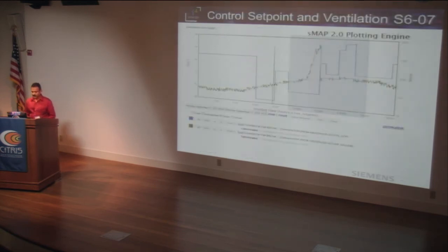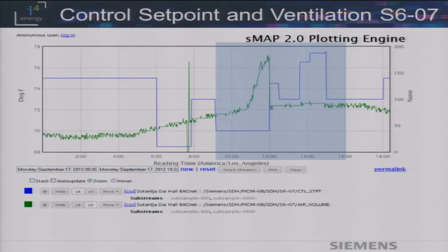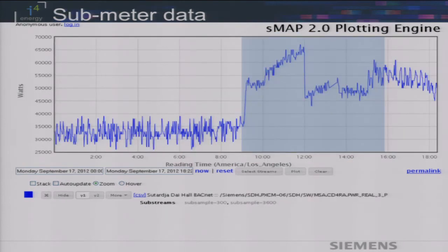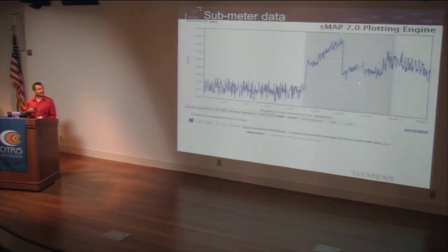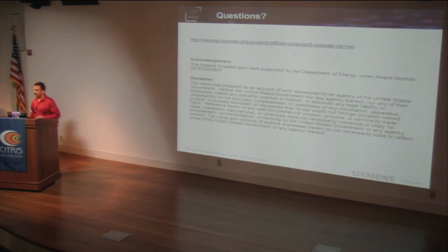So this is a zone temperature set point and ventilation. I brought a couple of them to show here. The temperature set point was around 9-ish. We were pre-cooling, and then we raised it, and there was some interruption in between at the building management system. Then it was resumed, and it went up to near 78, 77 point something. And the flow, if you look at this, during the pre-cool it went up, and then it was minimized according to the set points. This is one of the submeters for the AHUs, and it shows, during pre-cooling again, it was consuming more, and then it went down during the DR time as well. So this is all the test results from yesterday's test.